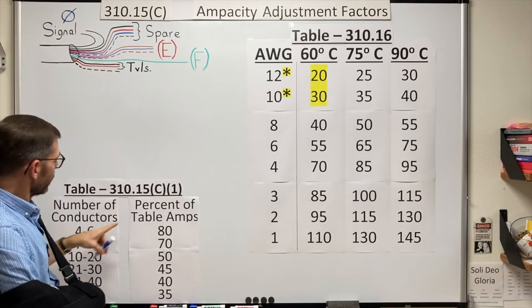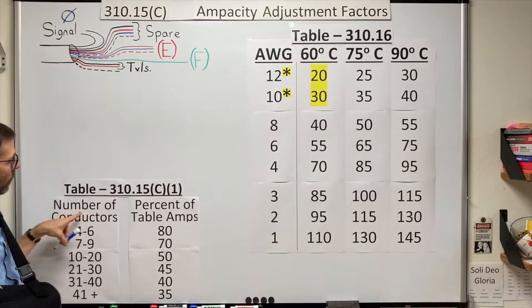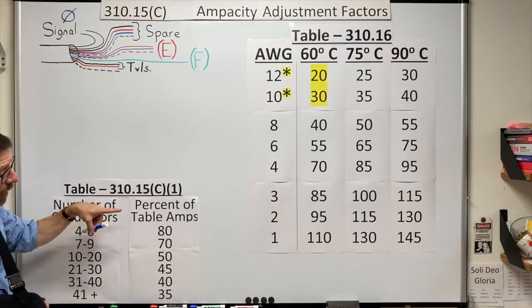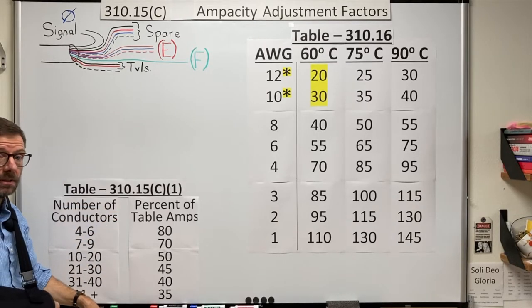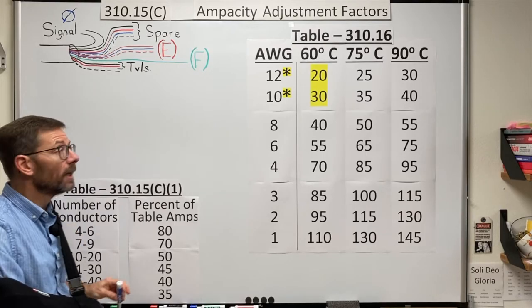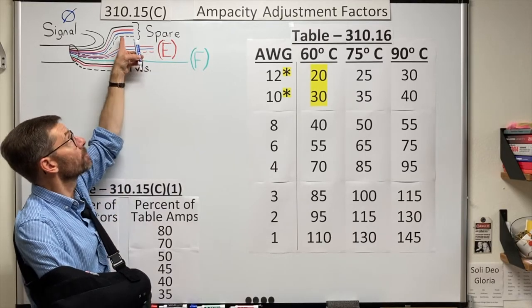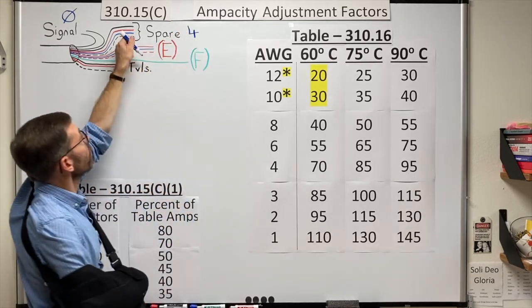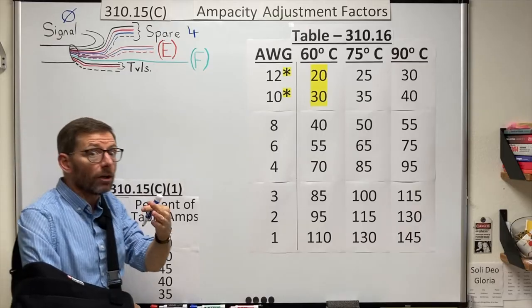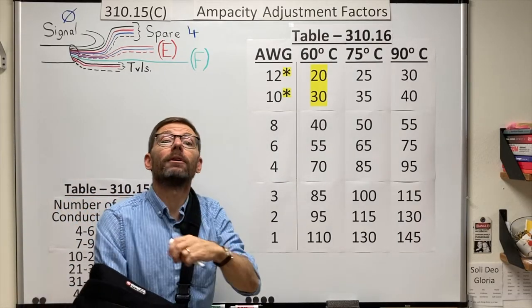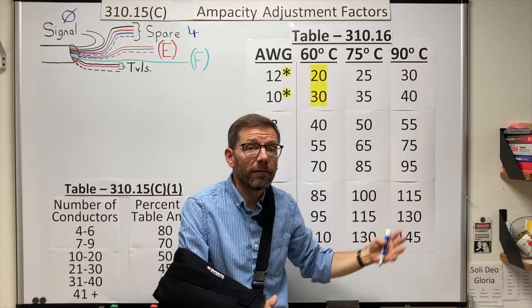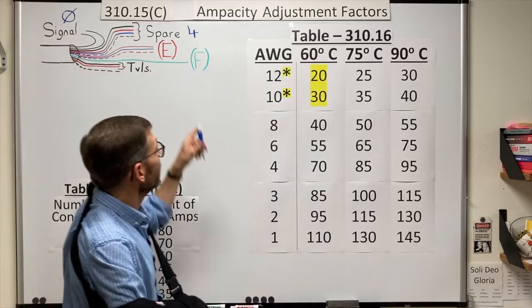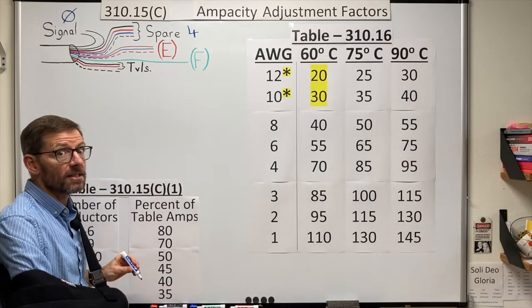Zero wires. However, there is an asterisk right beside the number of conductors on the table, and it refers to three sentences written below the table. The first sentence there tells me that if I have spare wires, I need to count all of them. So here I have four spare wires. I'm not using them now. They're not adding heat now. But when we do connect them in the future, I don't know what configuration they'll be used in, but they will start adding heat then. So I need to account for them in this stage of the process.